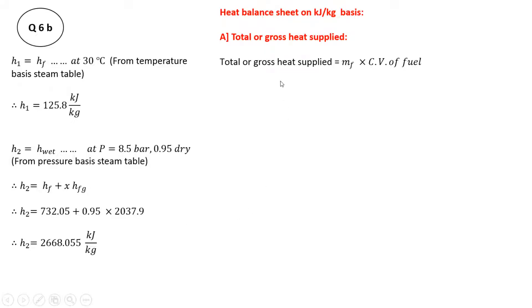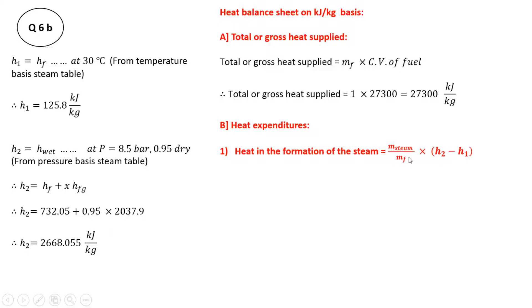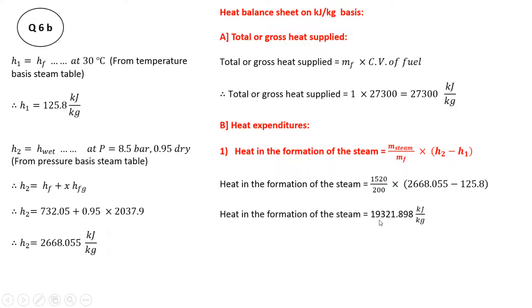The first part of the heat balance sheet is total or gross heat supplied, which is mass of fuel multiplied by calorific value of fuel. Since the heat balance sheet is on a per kg basis, mass of fuel is taken as 1 kg, so gross heat supplied equals 1 × 27300 = 27300 kJ per kg. Out of this total heat, some is used in steam formation. Dividing mass of steam by mass of fuel (1 kg) and multiplying by H2 minus H1, the heat in steam formation comes out to be 19321.898 kJ per kg.